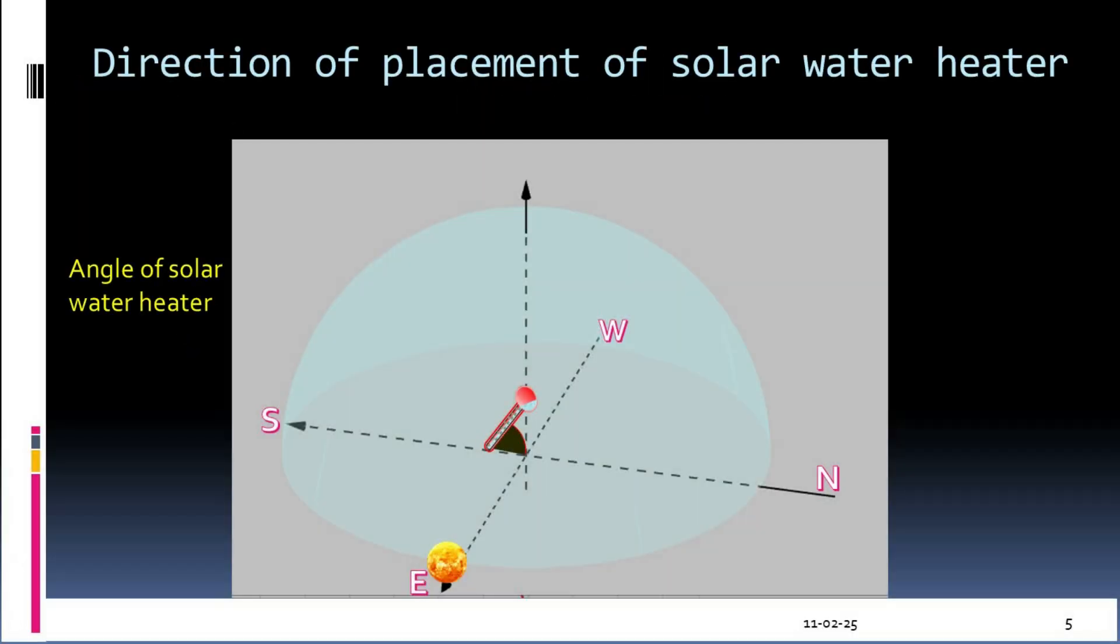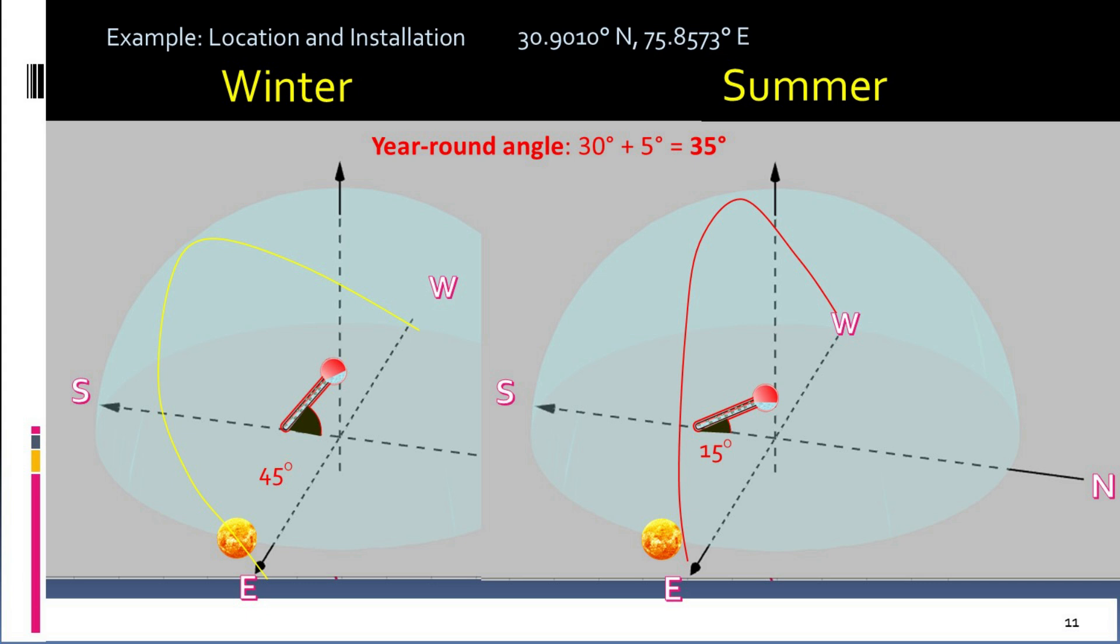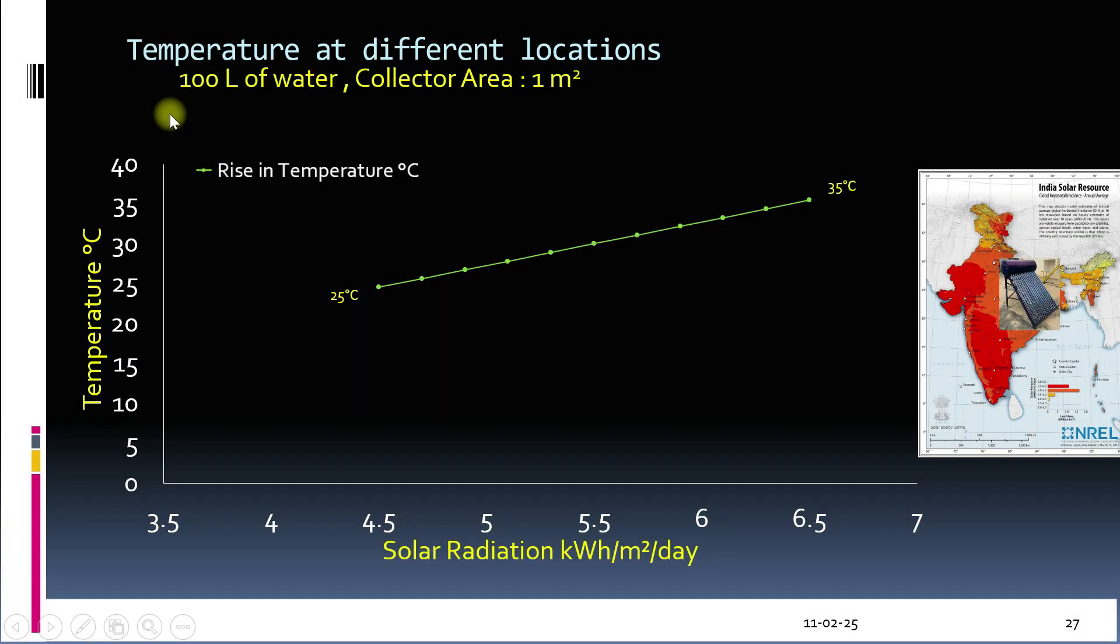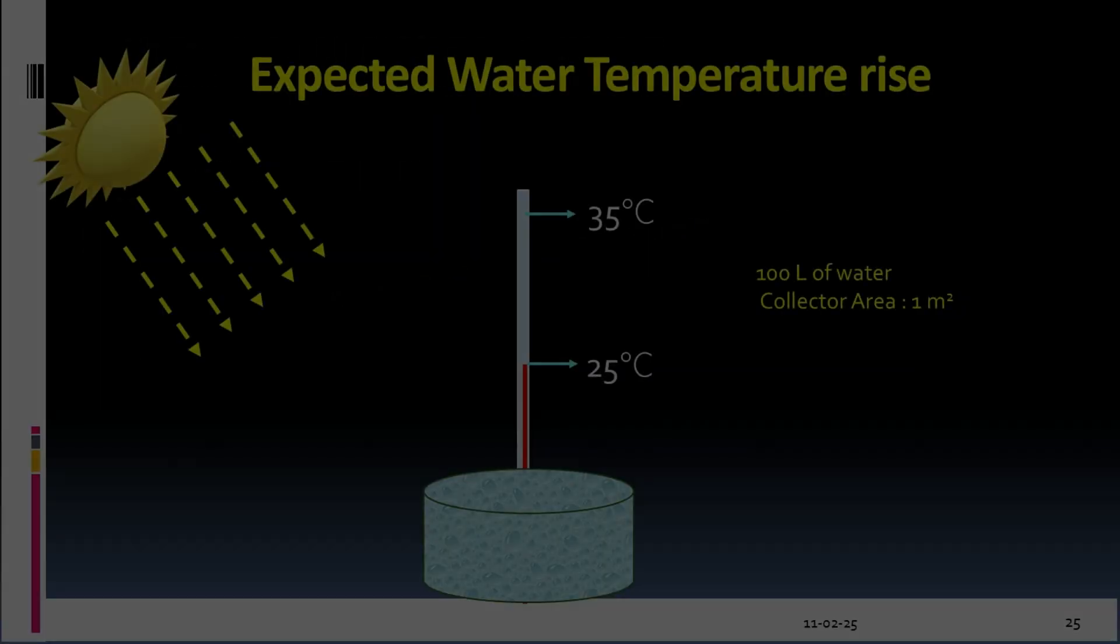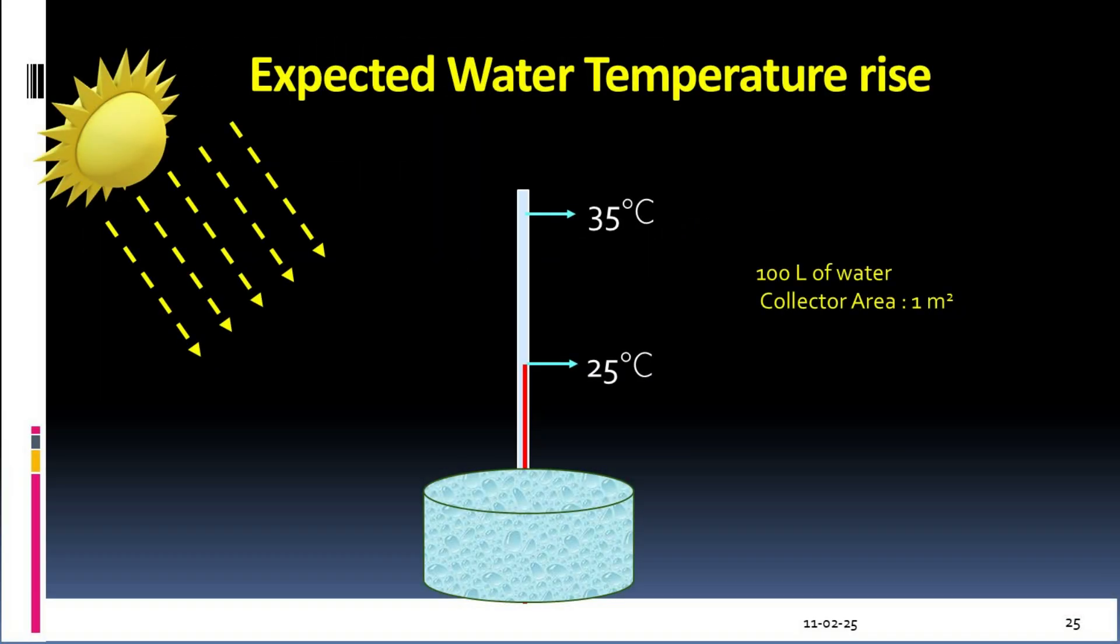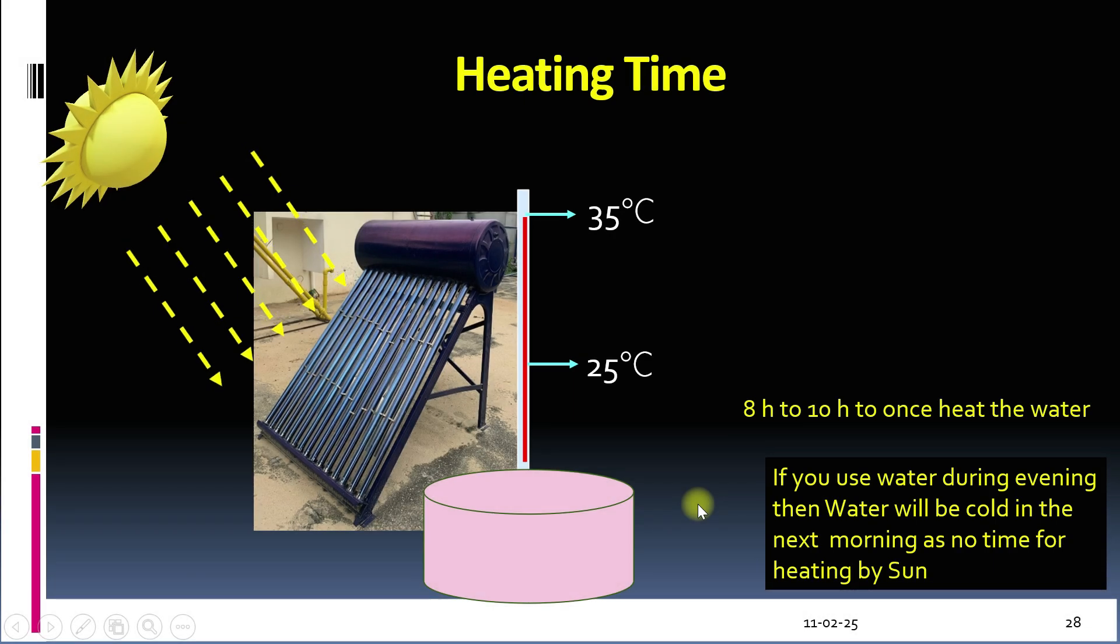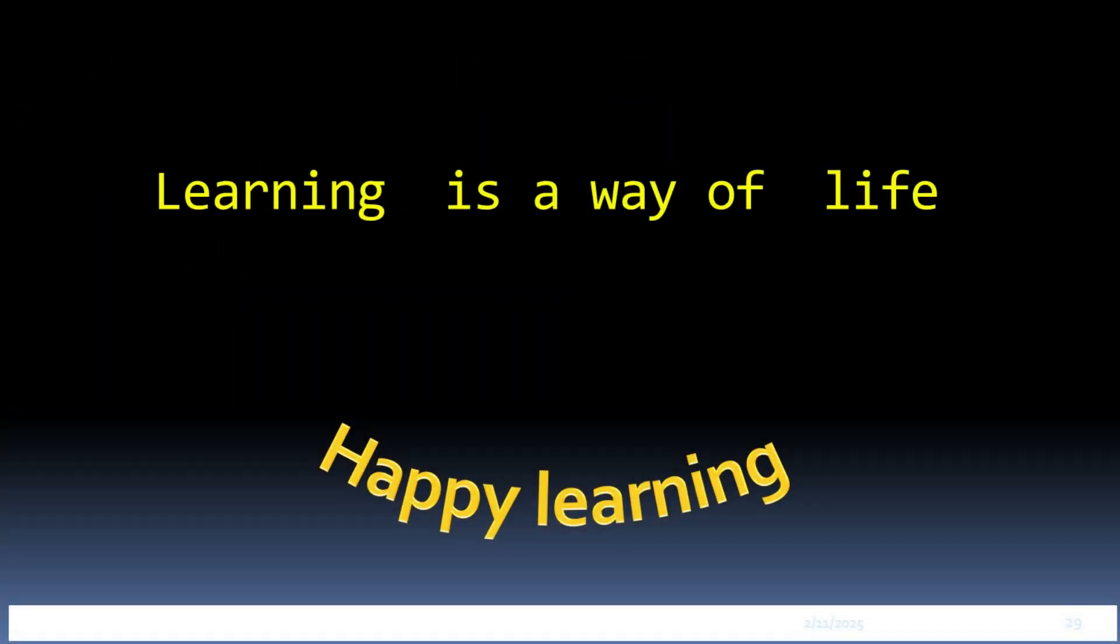So let's summarize. We have discussed that the solar water heater should face south in the northern hemisphere. We should adjust the angle based on the season. For example, latitude plus 15 degrees for the winters. The system operates on the thermosiphon principle and a temperature rise of 25 to 35 degrees Celsius per square meter per day for 100 liters of water may be expected during 8 to 10 hours of heating time. Thank you very much.